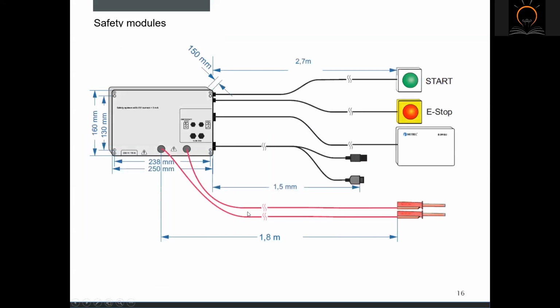The last one from the safety modules is the S2115 safety module with HV current limitation. So this one is enabling us to test with test currents below 3 milliamps, meaning that we are on the safe side and we can omit requirements from EN 50191.